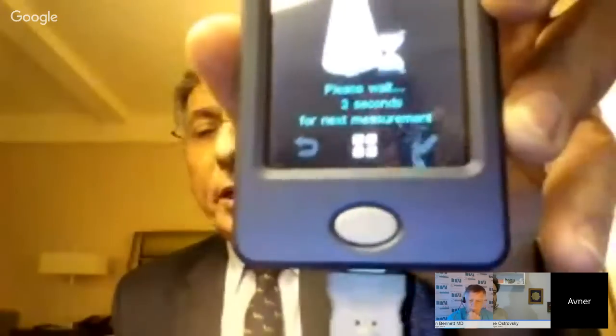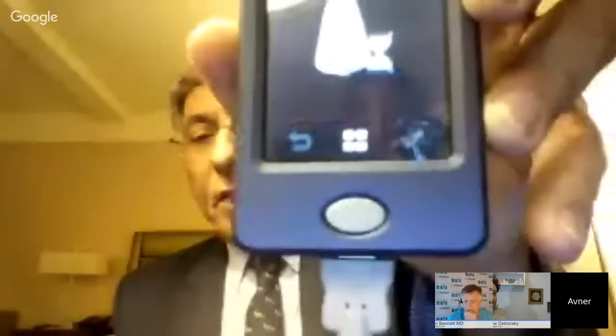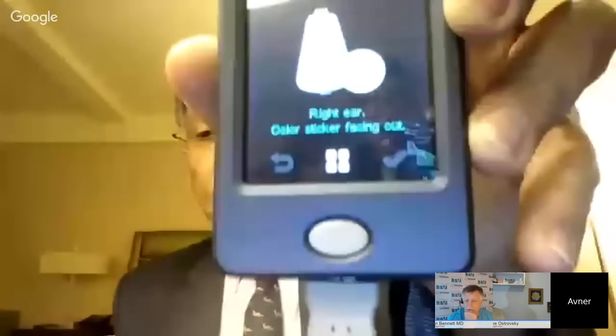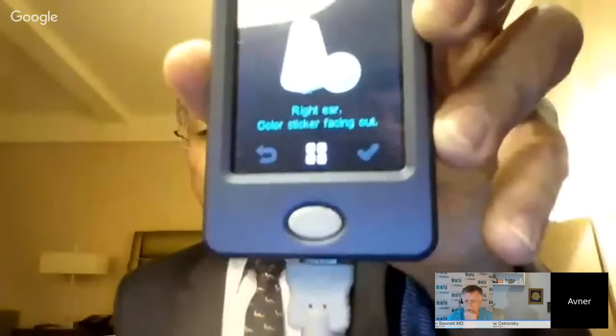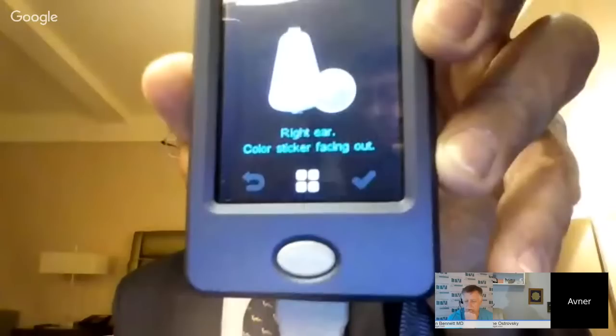It takes about 10 seconds for the device to communicate with the ear clip, to check that everything is okay, and then that also this particular ear clip is calibrated. I'm not sure if you noticed, but it says right ear. It also said right ear. It reminds me that I was calibrated in my right ear. The only thing that I have to do now is just to clip the ear clip to my earlobe, as you can see right here, and the device starts measuring.